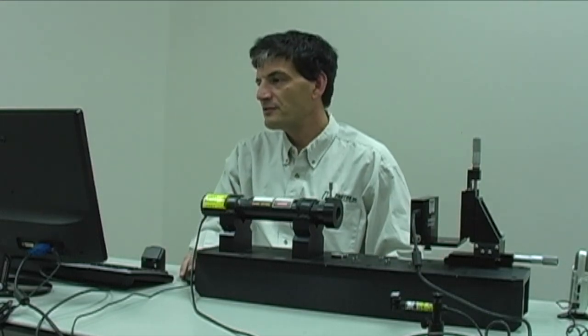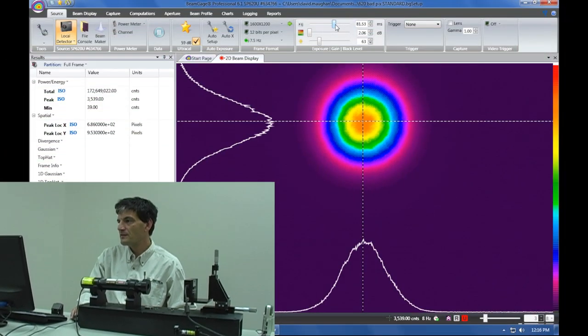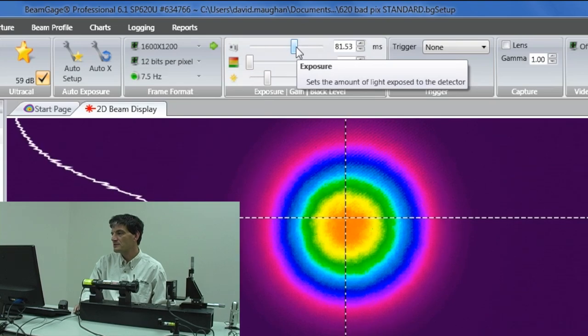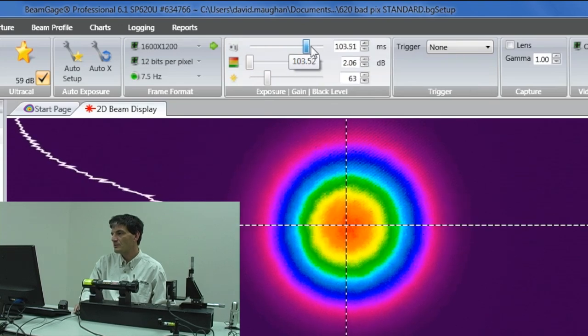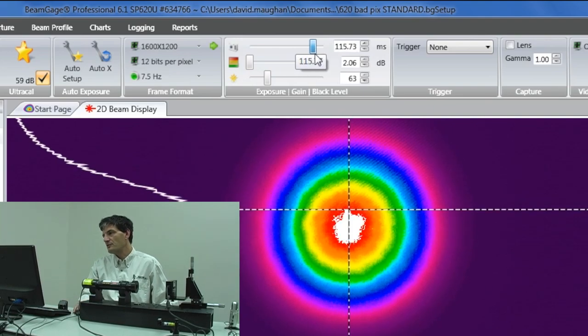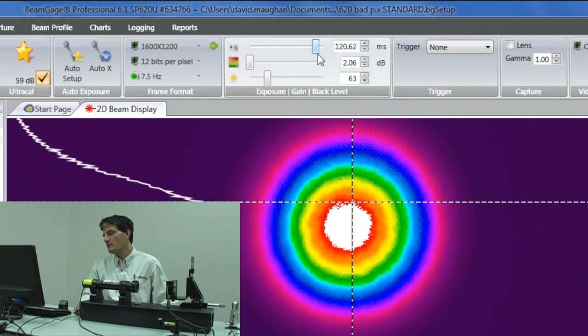A final way to adjust the beam attenuation, or at least the sensitivity of the camera, we do allow you to control the integration time of the camera. You can see as I move it back and forth, what happens is you can see sort of a white area as I increase exposure time.